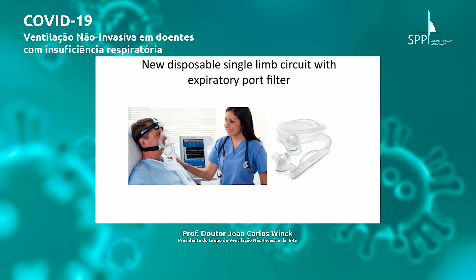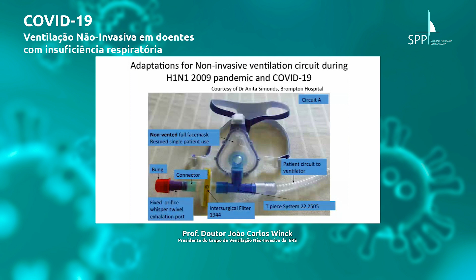So not with the single limb active valve like the ones that I showed you at the beginning. This is one single limb without an active valve, but with a normal expiratory valve, a kind of whisper swivel. This is the solution that in the UK, the group from the Brompton has shown to let people use these kinds of circuits with more safety. They have done a nice study about the droplets that come out from the patient on NIV like this, and with this simple expiratory port with the filter, they have decreased the number of droplets coming from the patient. So this is another option.